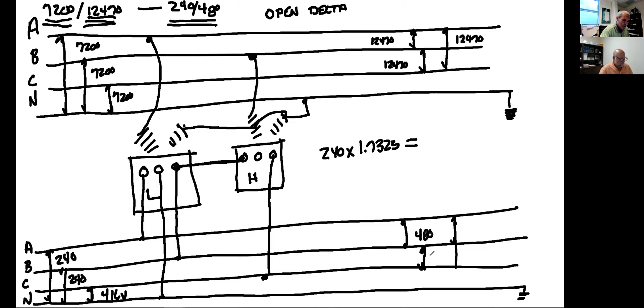Is that right? Yep. So my C to neutral is 416 volts. Phase to phase, A to B, B to C, A to C. You notice I did it just like I did my primary lines. Trying to keep things kind of in order here. Real simple on this one, 480, 480, and A to C. Sorry about that. Double line there, 480.